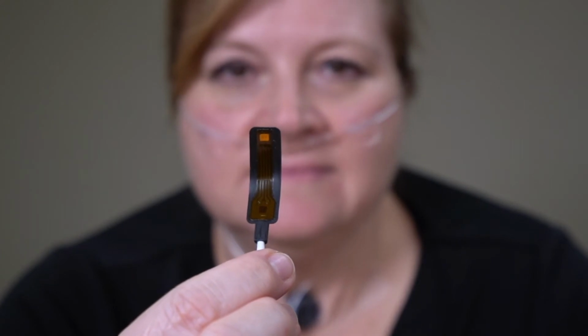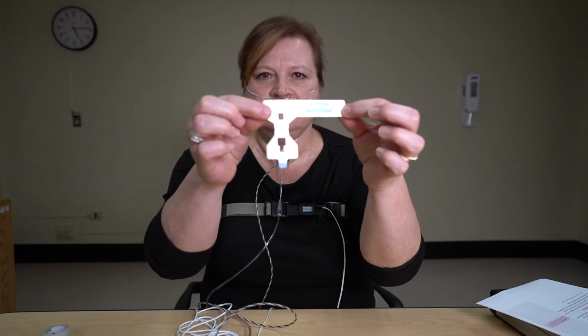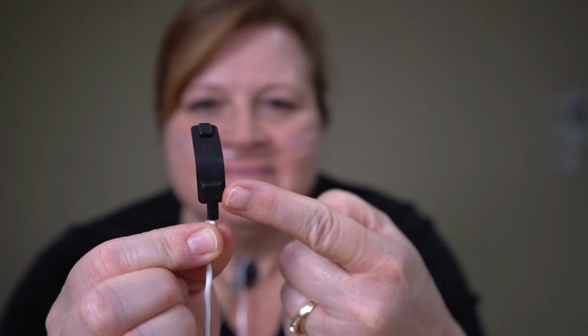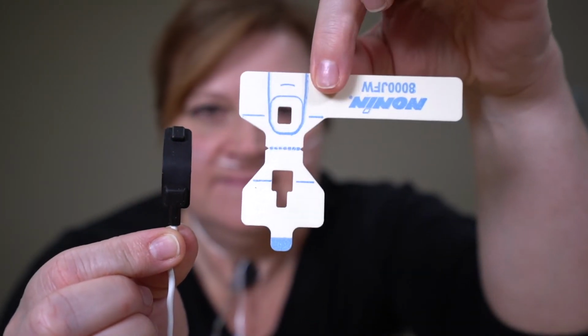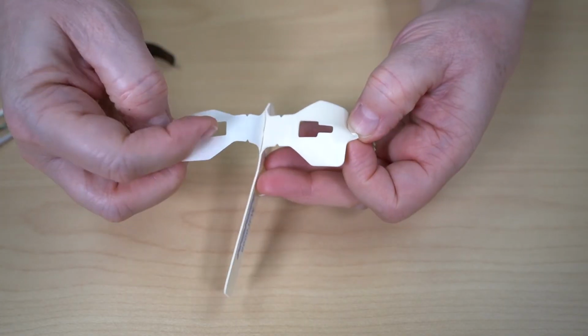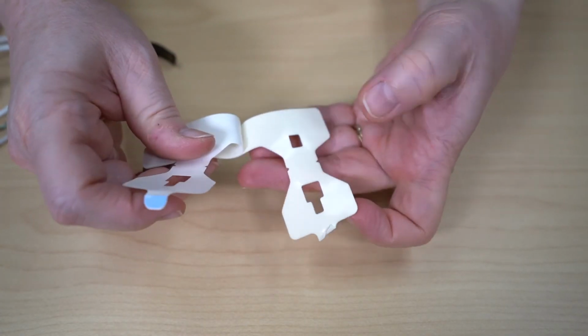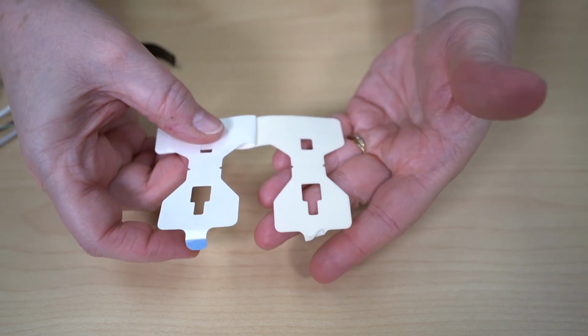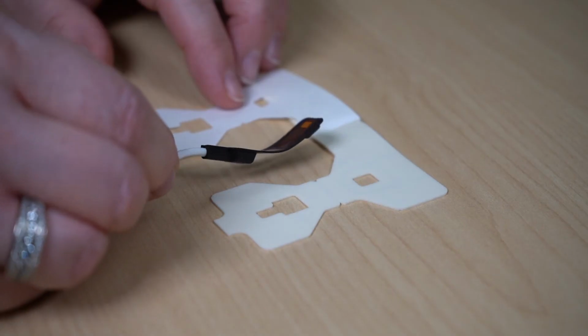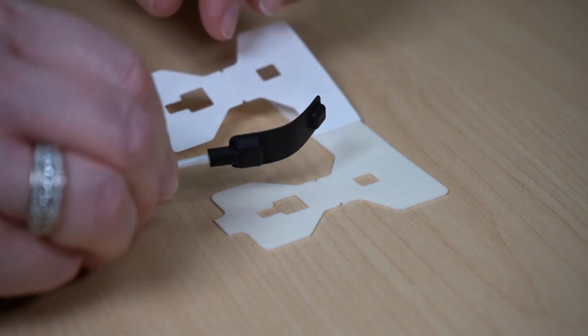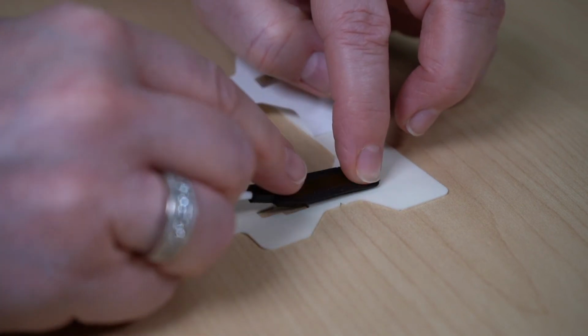You should see a red light on the finger sensor. You can use your left or right hand and will apply the finger probe to an index or middle finger. You will use the finger wrap adhesive to secure the probe to your finger. There are 2 squares on the back of the finger probe and 2 squares on the adhesive wrap. Peel half the wax paper from the adhesive, exposing the sticky side with the squares.